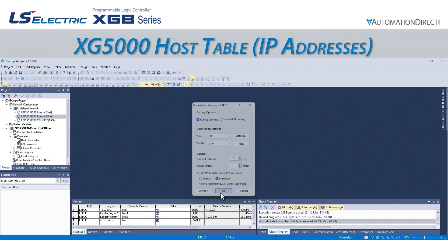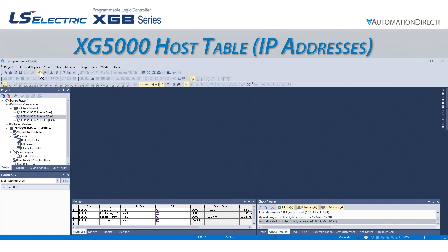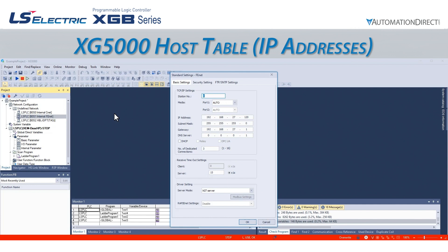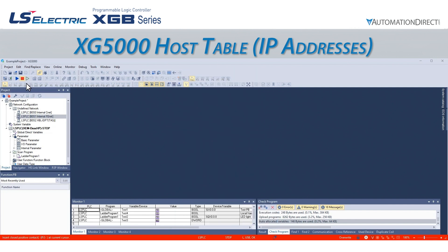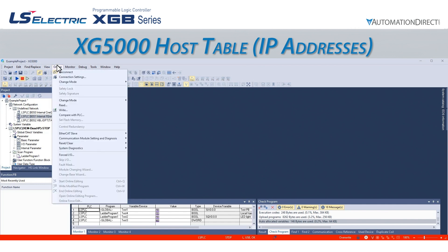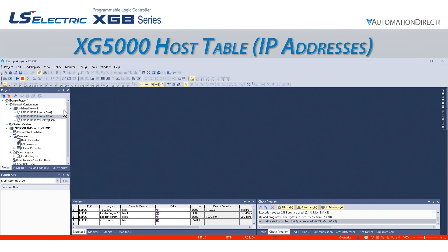To disable the host table, we connect to the PLC over USB or with an Ethernet device with an IP listed on the PLC's host table. Once we are connected, we can double-click on the Ethernet port with the host table we want to disable. This opens the same standard settings screen, and we can navigate to the Security Settings tab. If we uncheck the box for Enable Host Table and click OK, we can write the project to the CPU, and it will now accept access from any IP address via Ethernet.